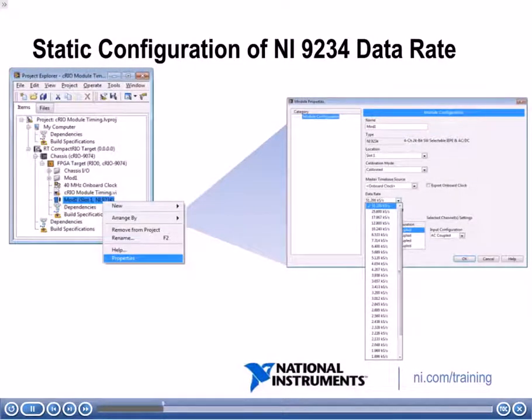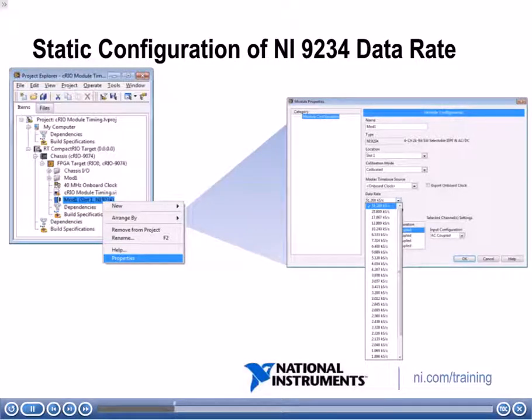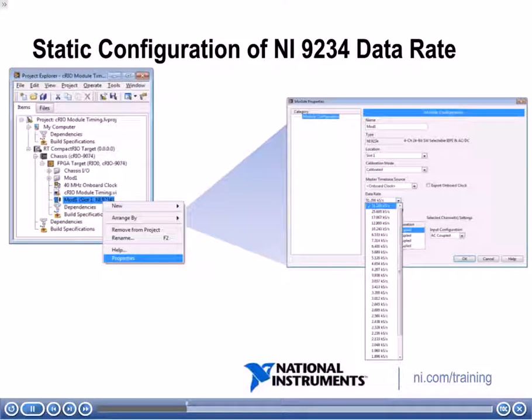This slide shows how to statically configure the NI9234 data rate. Looking at the project on the left, you can right-click module one, which is our 9234 module, and go to properties. Once you select properties, it opens a dialog where you can statically configure these properties. Notice that data rate is one of these properties, and you can select what rate you want to acquire data at — for example, 51.2 kS per second.